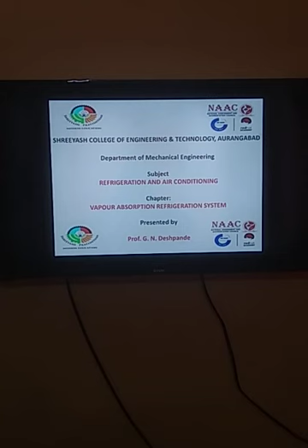pressure reducing valve. The simple vapor absorption refrigeration system means the theoretical vapor absorption refrigeration system. The components which we already discussed are used in this simple vapor absorption refrigeration system. The refrigerant absorbent pair used is called the aqua ammonia pair, that is ammonia as the refrigerant and water as the absorbent. The pump used in this theoretical system increases the pressure of the pair or solution up to 10 bar.